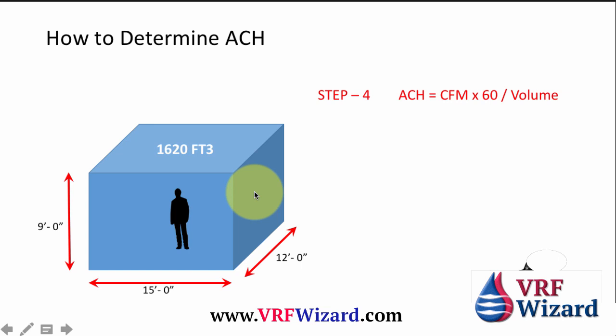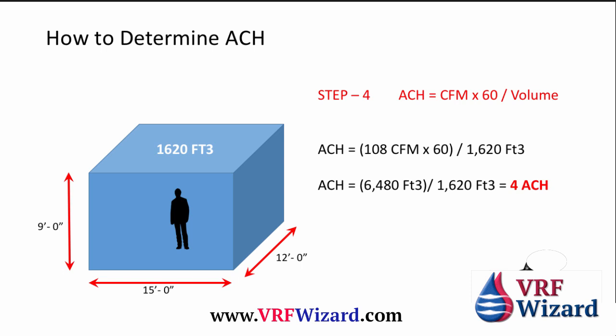If we need to work backwards and we know the CFM of the room but not how many air changes it is, we can determine how many air changes per hour a certain CFM is worth using this formula. Take the 108 CFM, multiply it by 60 minutes in an hour, and divide by the volume — that gives us the air changes. You can work it either way, forwards or backwards; the formula works the same.